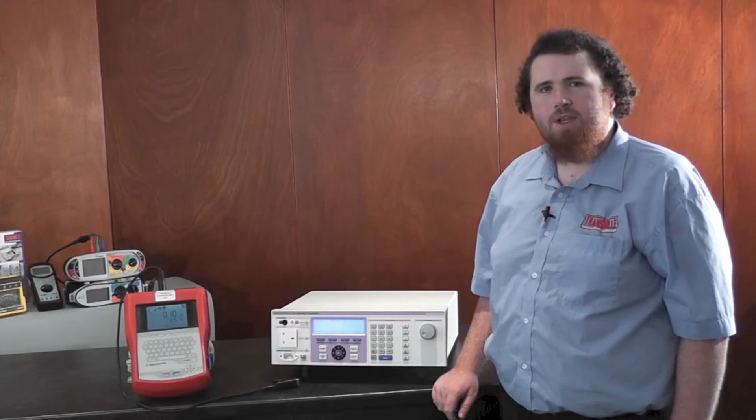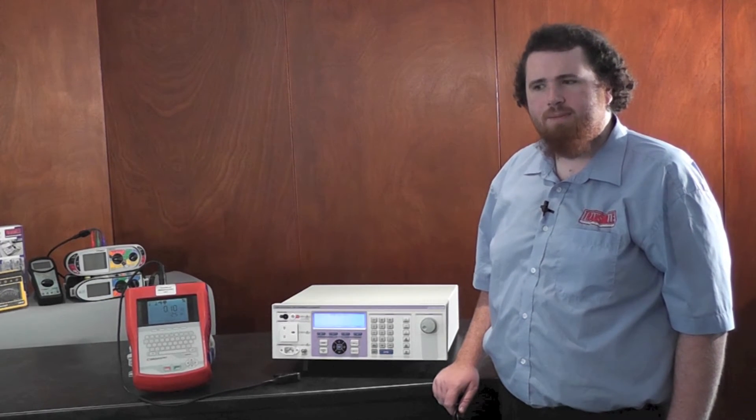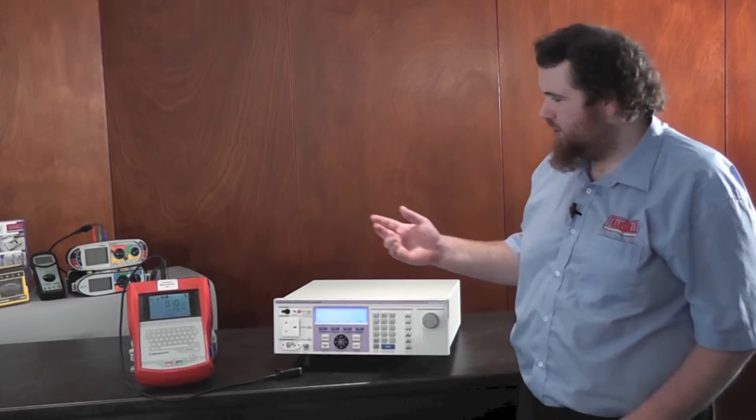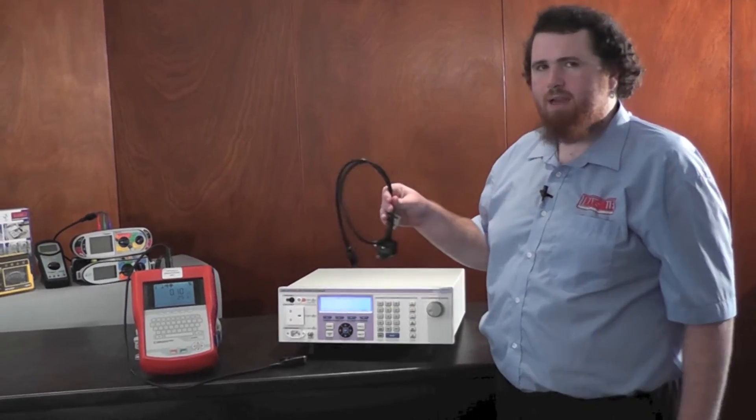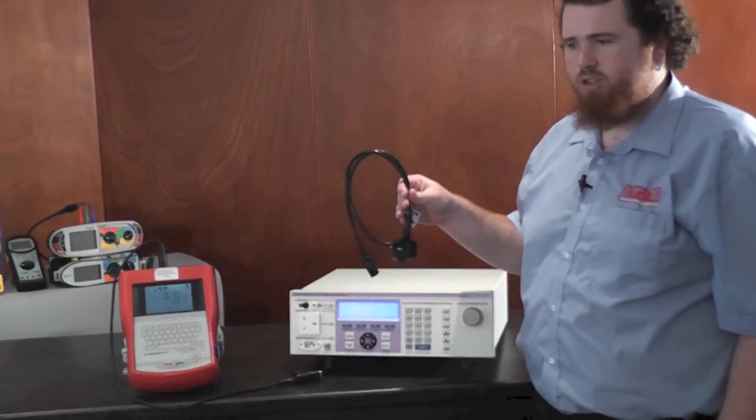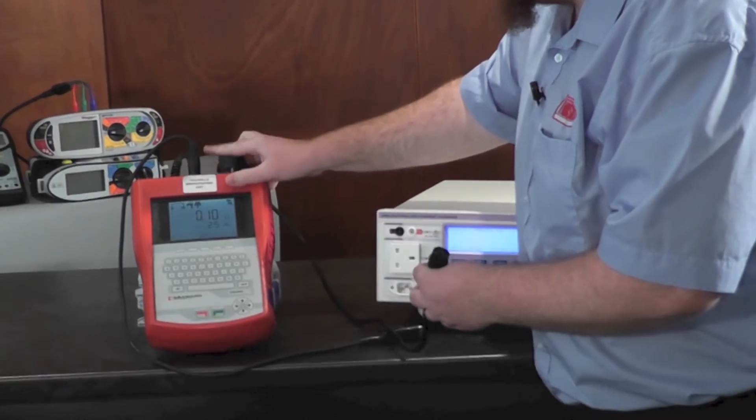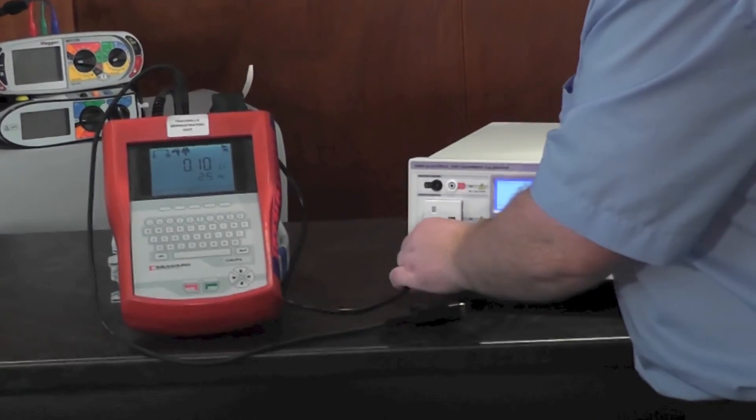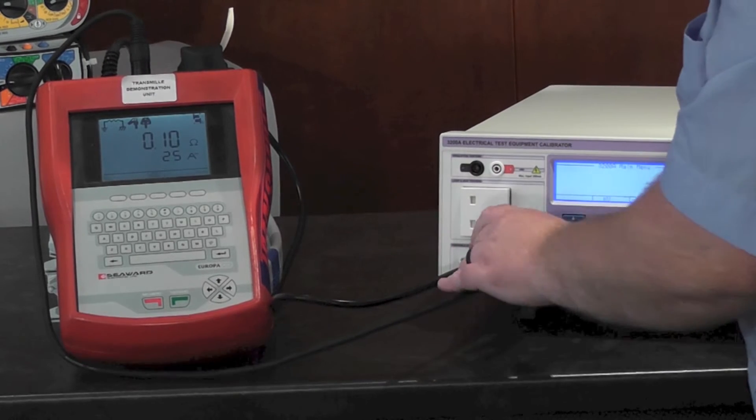The 3200A contains a comprehensive set of features for calibration of PAT testers. To show how simple calibrating a PAT tester with the 3200A, I'm going to calibrate the bond resistance on this unit. Using the calibrated lead supplied with 3200A, I'll connect up the PAT tester and connect the earth clip to the earth clip provided.